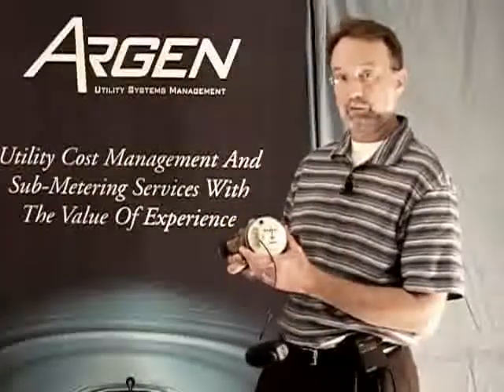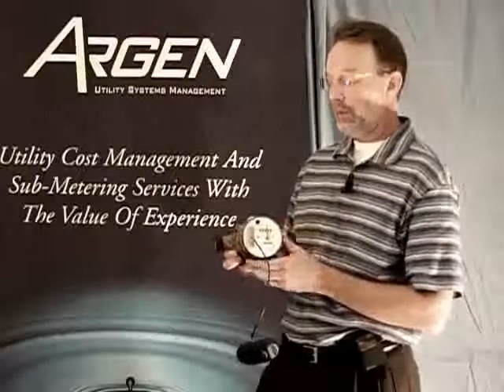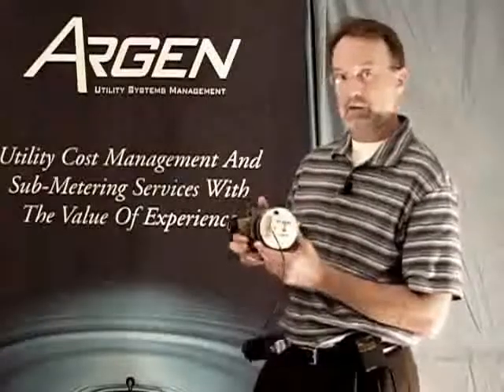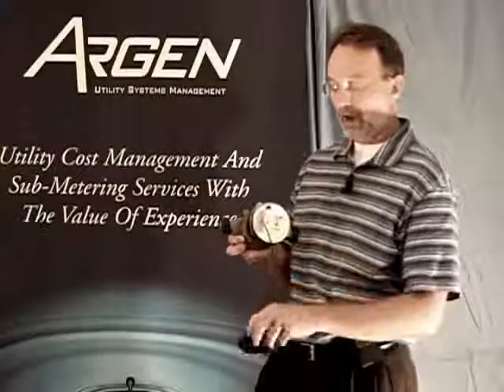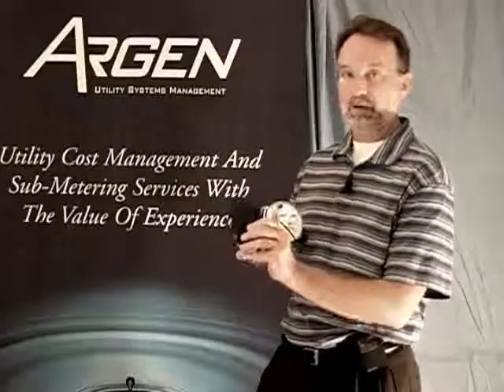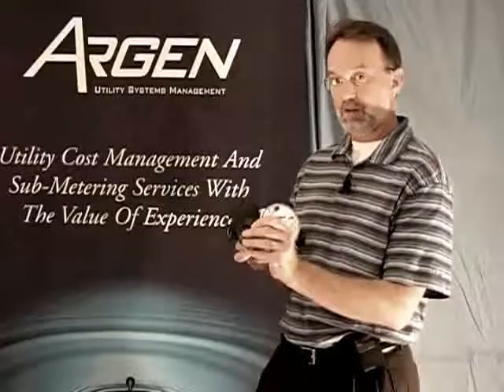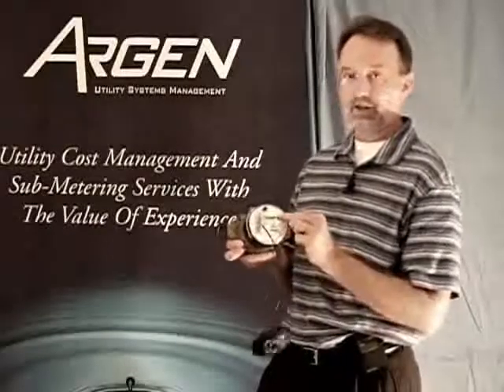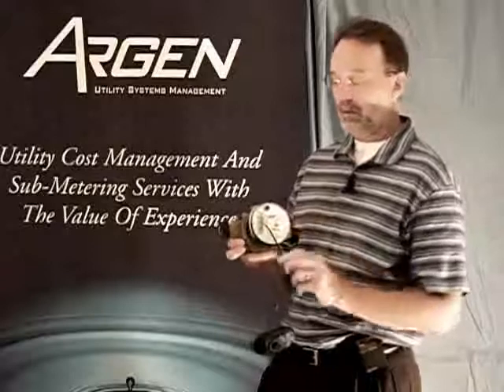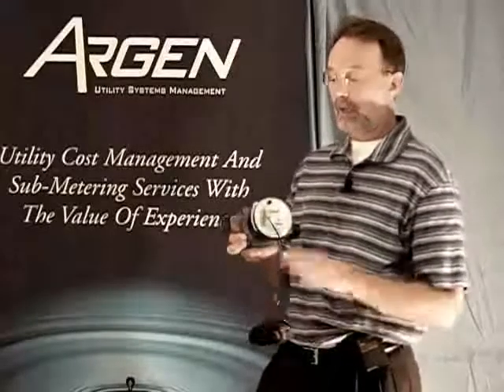Another method for water submetering is where we have an electronic encoded register head. The meter is installed inside the tenant space and is hardwired up to 500 feet away to a touchpad on the outside of the structure. The meter reader walks up, scans his touchpad, and automatically collects the data. The power source for this system comes from the handheld collector of the meter reader, and there is no power inside the register itself.